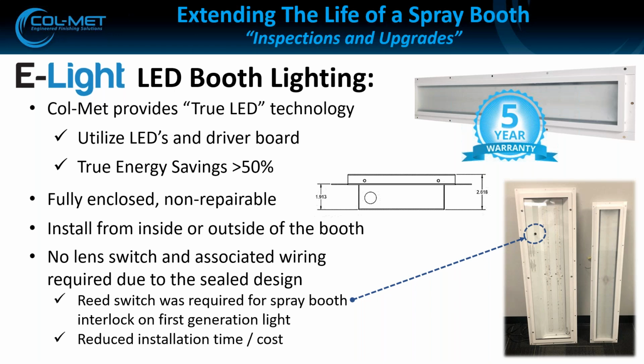If you're familiar with installing a lens switch, it's required by UL listings because the glass was made to be removed from inside the booth. It just guarantees that the cover got put back on. It isn't a glass break sensor, and the code doesn't require it to be such, but since the light was maintainable from the inside, you have to have something that confirms it got put back on.